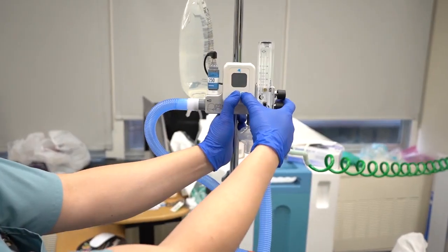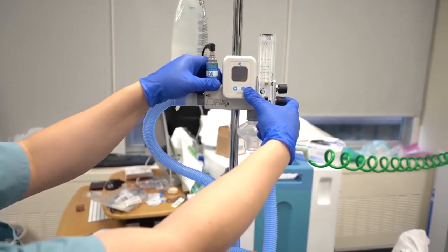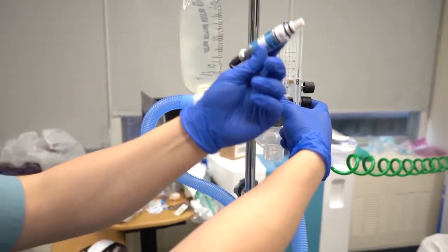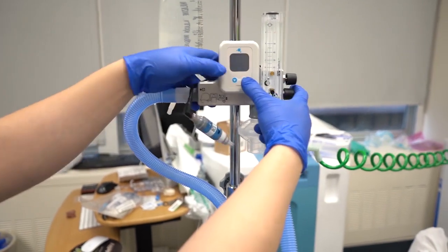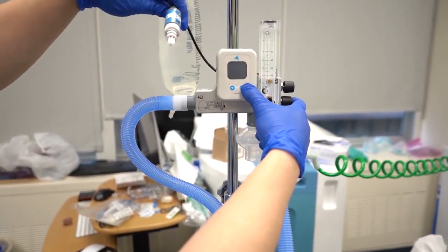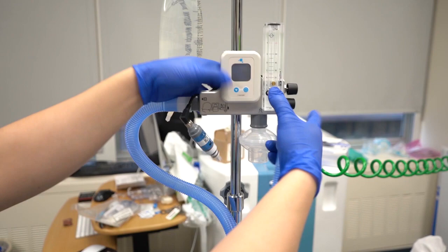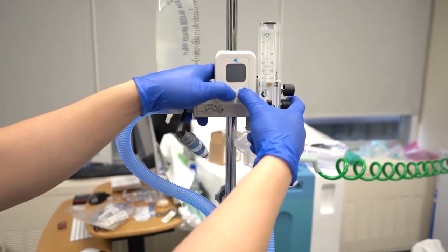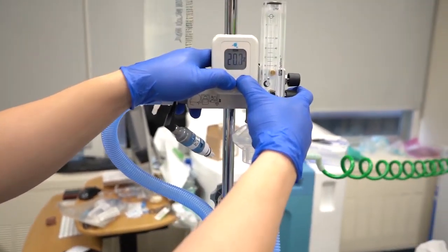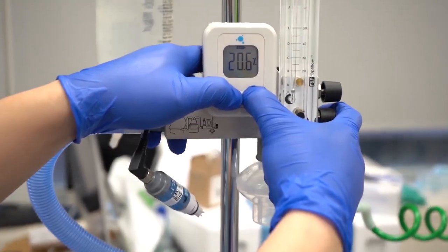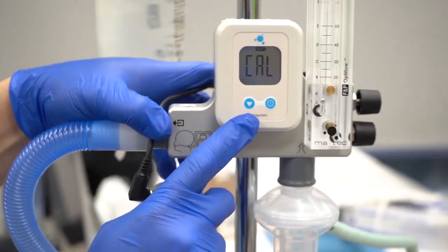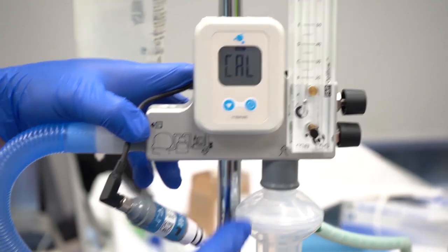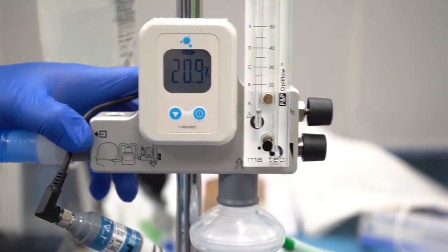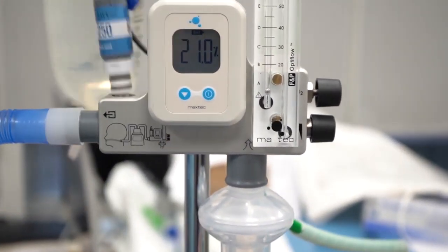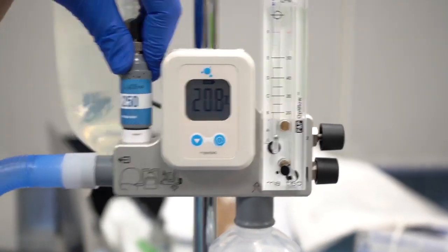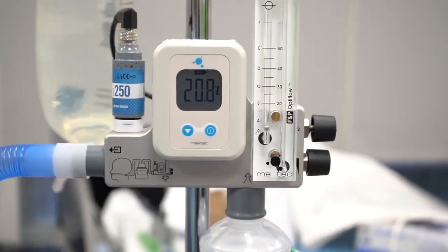And before we start, to calibrate the high flow, we're going to take out the oxygen sensor. This is your oxygen sensor. This measures the amount of FiO2 being delivered. You're going to take that out so we can calibrate to room air. To calibrate, you're just going to hold these 2 buttons together until it says cal. It's going to calibrate. It should be close to 21%. So 20.9. Once that's done, just put your oxygen sensor back in.